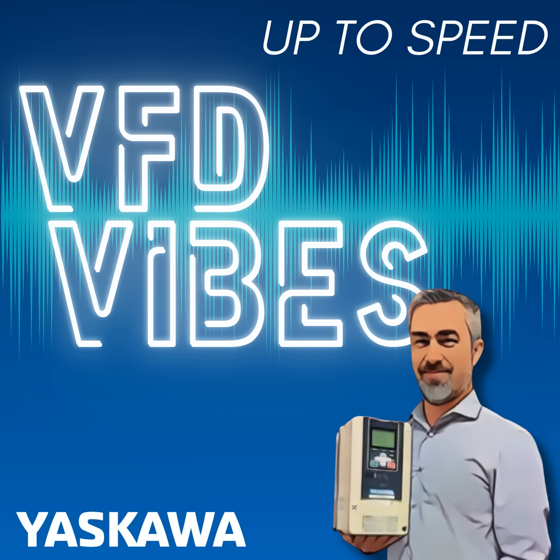The first and foremost is probably voltage distortion. So your system voltage is what all the other devices on that particular system see. And if excessive harmonic currents are distorting that voltage, you're impacting the power quality to other devices connected on your network.